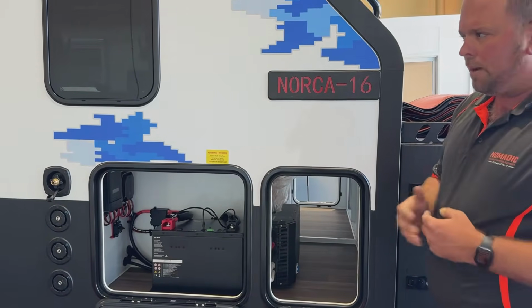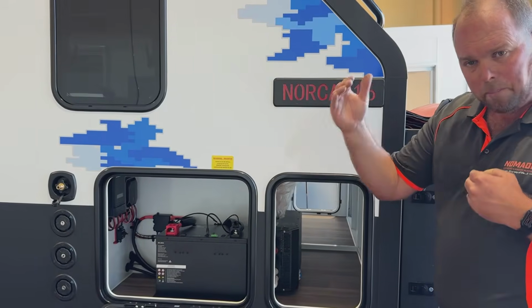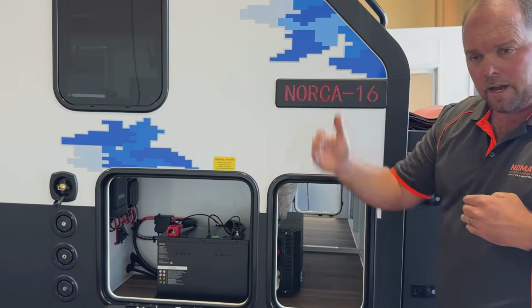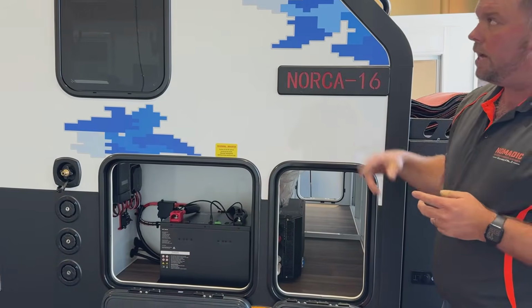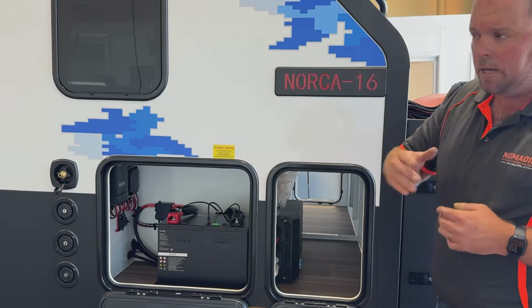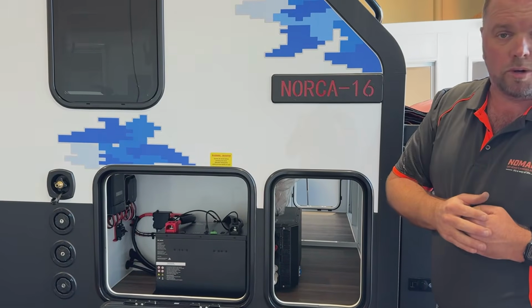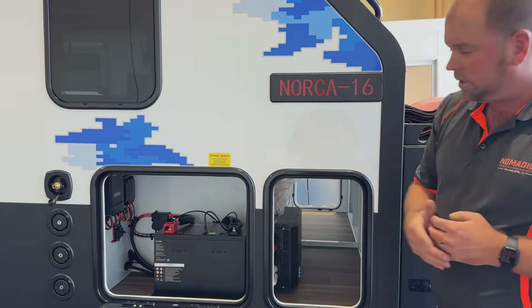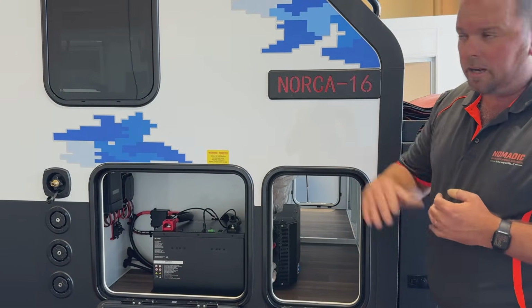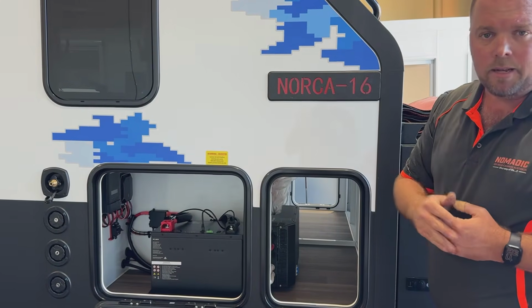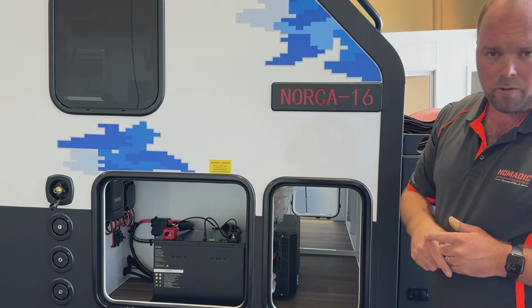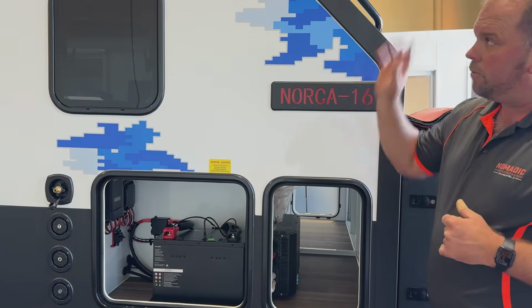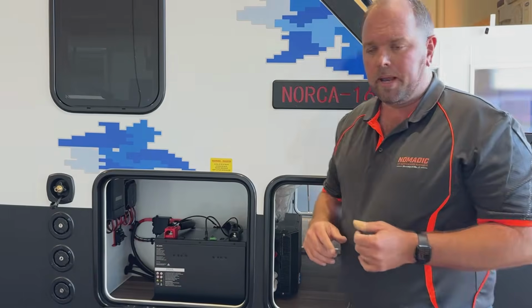So what that means is it will have a 4000 watt peak that it can operate under, and then it will wind back. So if you can imagine your aircon, when it first starts up, it will go to about 2400 watts. That inverter will handle it, and then it will slowly come back down to sit around about 800, 900 watts. So that's its operating point. We use a very smart aircon with the Nomadic system.